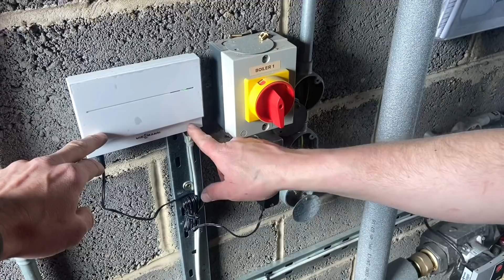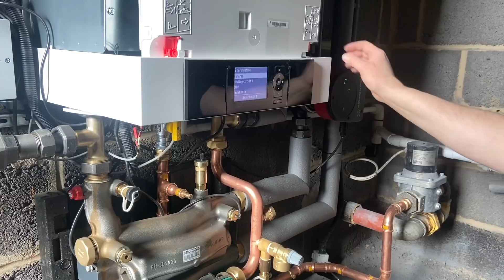Okay, let me sit down. So you just talk us through. So on here we've got outside temperature, inside target temperature, and if we go into information, we can see we've got a heating circuit, which is the pump, and hot water. The cylinder's currently 60. If that was below its set point, obviously that pump would be on. We're also controlling the circulation pump as well, secondary side. Heating, we've got room temperature, reduced temperature of 13. I've set the curve up for the weather comp to 2 on this because the ladies upstairs wanted the office quite warm. But we can alter all of this through here.